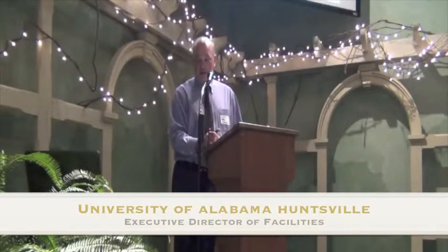I can generate a million BTUs for $3.55 or whatever it says, versus natural gas. It's kind of hard to believe that I can take electricity and generate a million BTUs for much less than natural gas, which is the tradition. I just happened to be in Charlotte, North Carolina a year or two ago, and I got to talk about this application. They said, if you can give me a month or two out of the year, I can have this machine pay for itself. Well, we're going to be able to give them 8 or 9 months out of the year, because if we reset our hot water based on outside air temps and hot water valve position throughout the buildings, we're hoping to keep these machines online for 8 or 9 months.